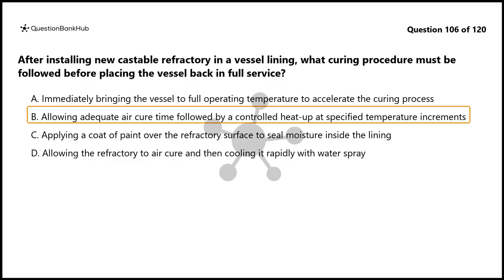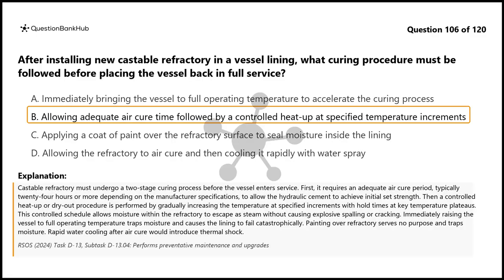The correct answer is B. Castable refractory must undergo a two-stage curing process before the vessel enters service. First, it requires an adequate air cure period, typically 24 hours or more depending on the manufacturer specifications, to allow the hydraulic cement to achieve initial set strength.